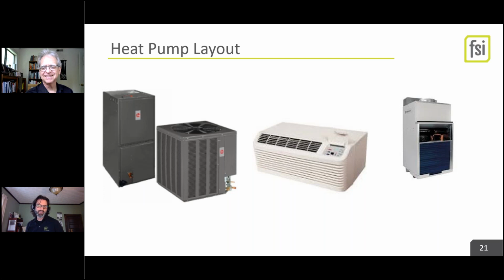Oh yeah, so this is my special note on compressors, and we kind of already alluded to this, but what you're seeing on the page here are the cheap versions. They're single speed compressors, and they have a real limitation on how cold it can be outside before they stop working. So Duane talked about 45 for PTAC. You know, some of these go down to 25. If you've got a heat pump in your house, it probably goes down to 20 or 25, and then you use emergency heat, which is just a fancy way of saying electric resistance heating, COP of 1. Let's go to the next slide.